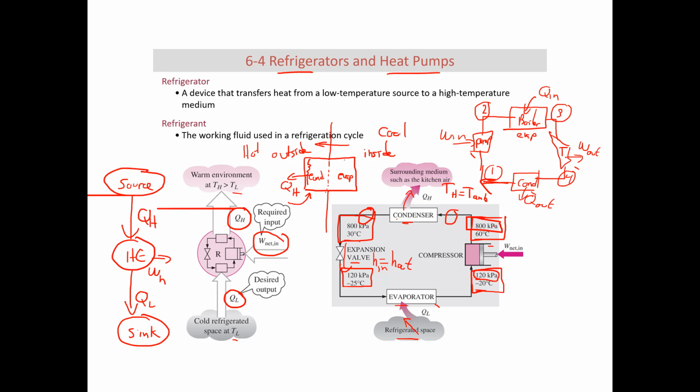condensing, it condenses at a saturated state, right? It's turning from gas into liquid. As it does that, I need to make sure that the phase change temperature, that saturation temperature, is higher than the outside temperature of the air. So let's say that the saturation temperature is 150 degrees Fahrenheit and the outside temperature is 100 degrees Fahrenheit. I'm going to reject heat to the outside, where that heat rejection is going to cause that refrigerant to turn into a liquid. So now I've rejected the heat outside.